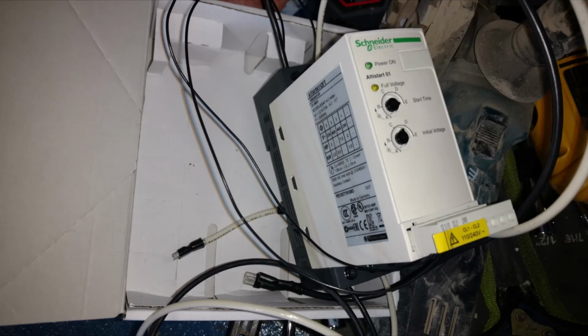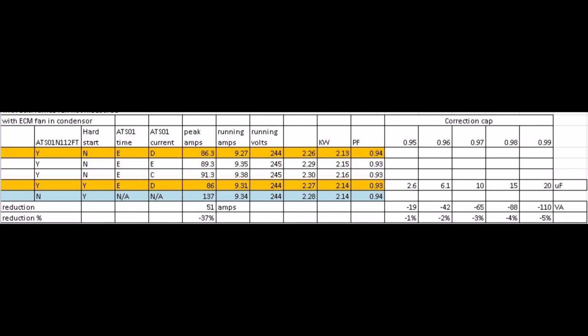My first idea was to reduce the peak current draw of the compressor pump when starting by installing an industrial motor soft starter. There are a few available for 1-phase motors, and I bought what I thought was the best one. After a short test period, I was able to reduce the startup current draw from 137 amps at 240 volts to 86 amps at 240 volts. The only problem is that 86 amps is still too much for the Magnum to provide all up by itself. It can only give 40 amp surge, and that's under perfect laboratory conditions.